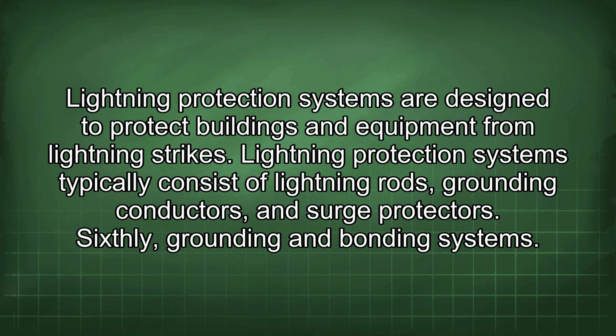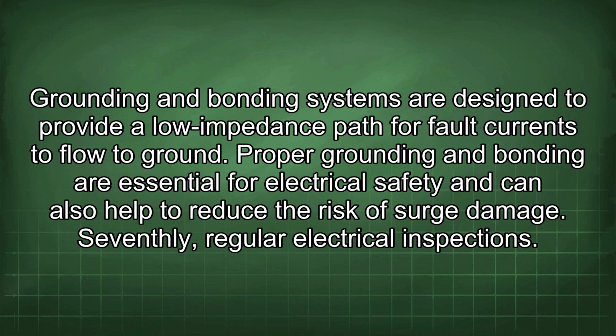Sixthly, grounding and bonding systems. Grounding and bonding systems are designed to provide a low impedance path for fault currents to flow to ground. Proper grounding and bonding are essential for electrical safety and can also help to reduce the risk of surge damage.